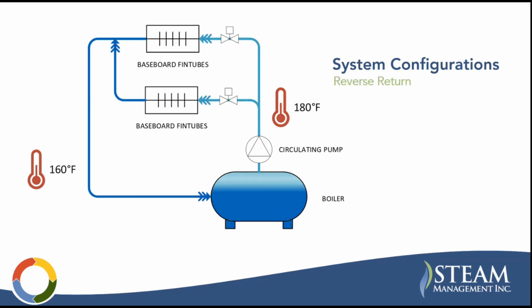So this is reverse return. You're getting a little bit better design than the direct return. Basically, it's the same idea, but your return line is coming from your more remote unit or emitters. The downside here is you've got a little bit more piping. But on the plus side, you're relying a little bit less on your balancing valves because it's more naturally balanced through the system. And so you should have a little bit less pumping energy because you're not having to throttle that flow so much.